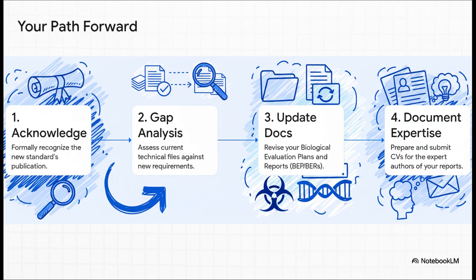So here is your path forward. Step one, formally acknowledge the standard is published within your systems. Step two, immediately perform a gap analysis on all your existing products and your technical documentation. Step three, start updating your biological evaluation plans and reports to reflect this new risk-based philosophy. And step four, and this is a new point of emphasis you really need to hear, you must document the expertise of the people writing these reports. Be ready to submit their resumes and qualifications.